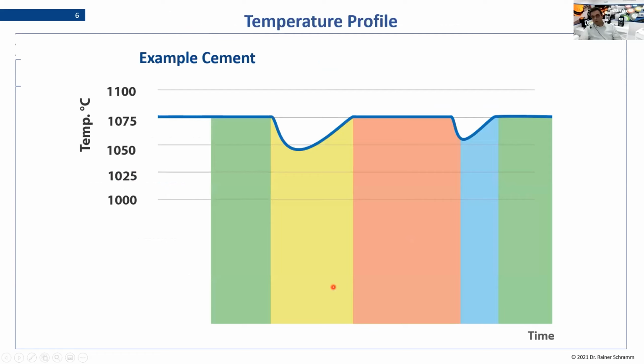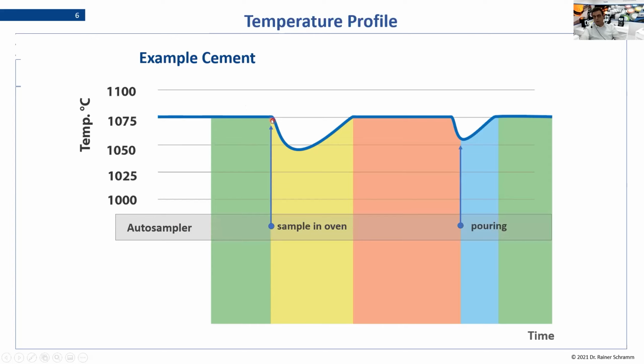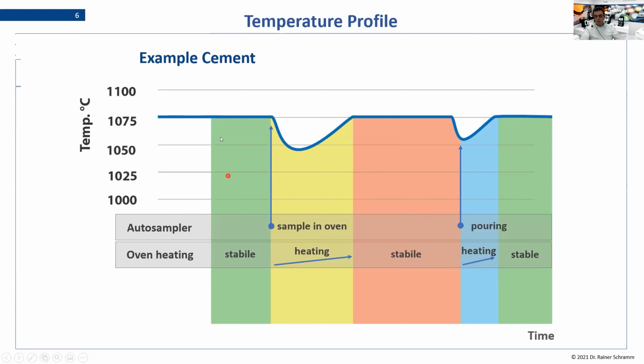But let's have a deeper look at temperature, because that is, in my opinion, one of the most important parameters. I would like to give you an example. Cement, perhaps diluted 1 to 10 or 1 to 8. You can fuse this, for example, at 1075 degrees. The moment the autosampler introduces a sample, the temperature will drop because you open the furnace. You introduce your sample, you close your furnace, and then the temperature goes up again. It's stabilized. Then for pouring, you have to open it again, same situation. The heating makes sure that your furnace is at the same temperature, and the moment you destabilize it, the heating must come back to the same temperature as before. Again, stability in temperature, and when it's stable again, you can make your next fusion. So this is the general procedure.